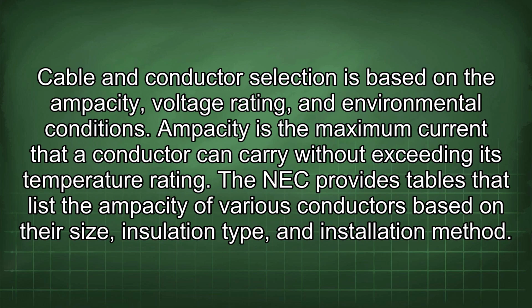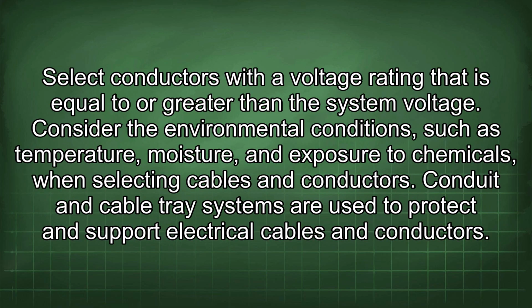Cable and conductor selection is based on the ampacity, voltage rating, and environmental conditions. Ampacity is the maximum current that a conductor can carry without exceeding its temperature rating. The NEC provides tables that list the ampacity of various conductors based on their size, insulation type, and installation method. Select conductors with a voltage rating that is equal to or greater than the system voltage. Consider the environmental conditions such as temperature, moisture, and exposure to chemicals when selecting cables and conductors.